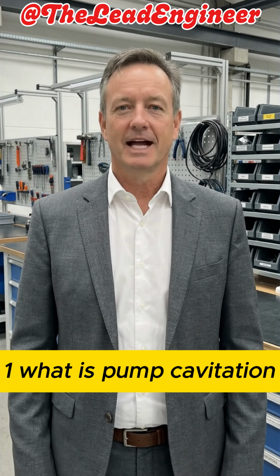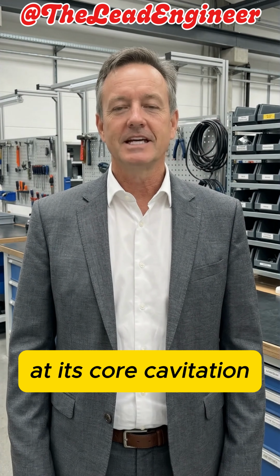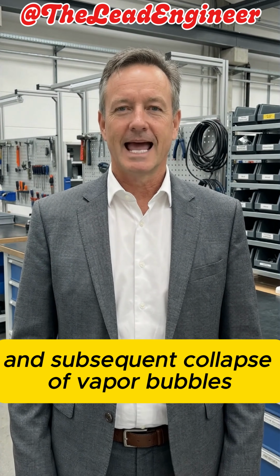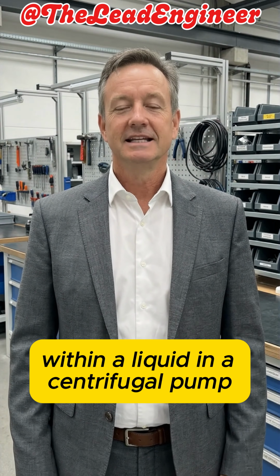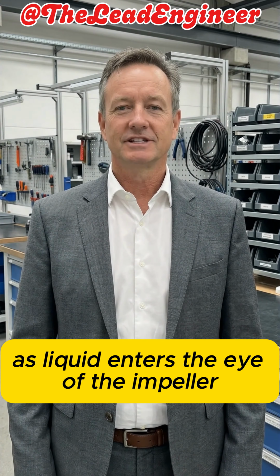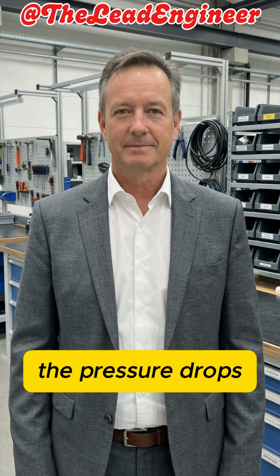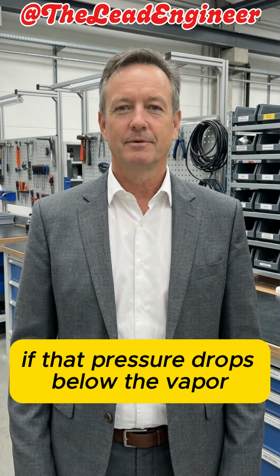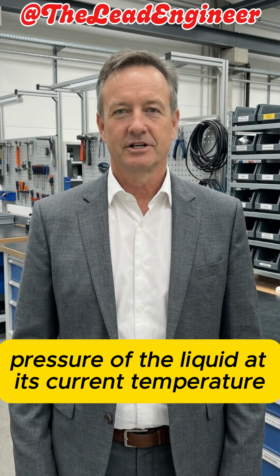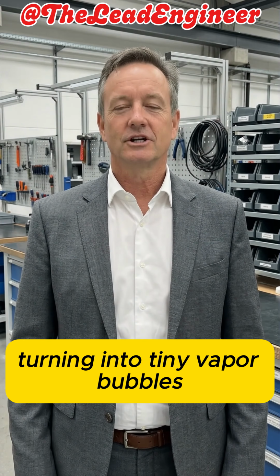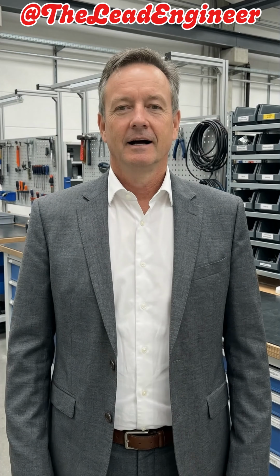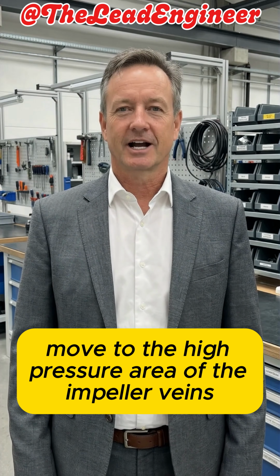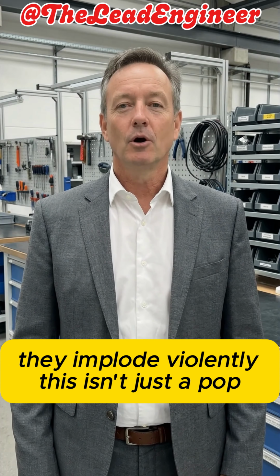1. What is pump cavitation? At its core, cavitation is the formation and subsequent collapse of vapor bubbles within a liquid. In a centrifugal pump, as liquid enters the eye of the impeller, the pressure drops. If that pressure drops below the vapor pressure of the liquid at its current temperature, the liquid literally boils, turning into tiny vapor bubbles. When these bubbles move to the high-pressure area of the impeller vanes, they implode violently.